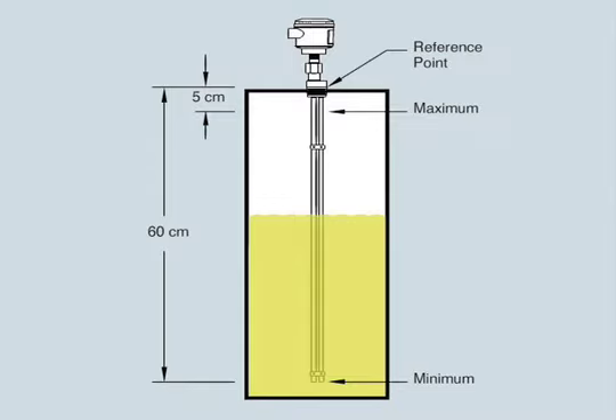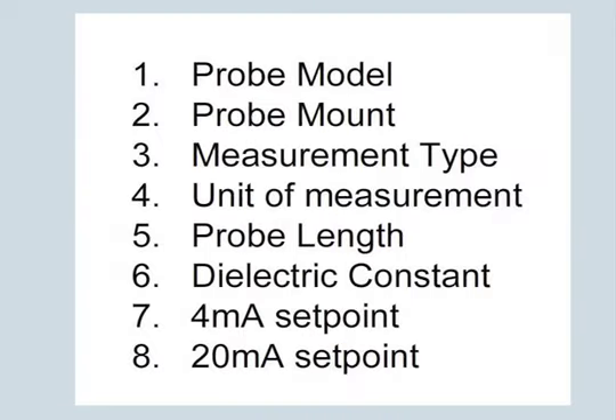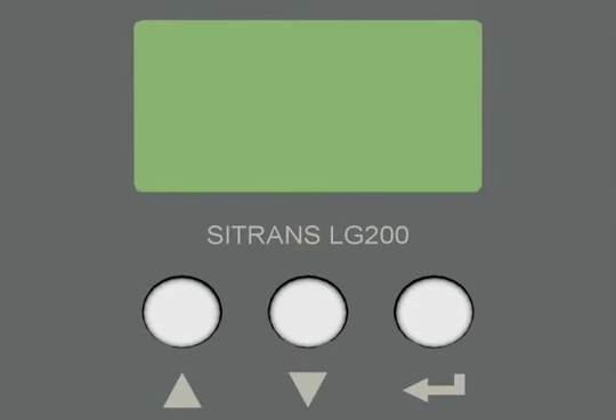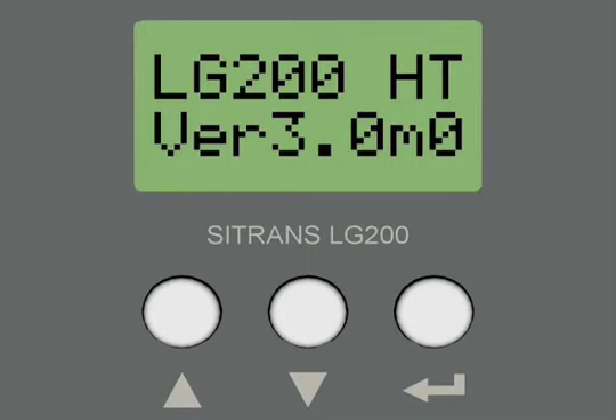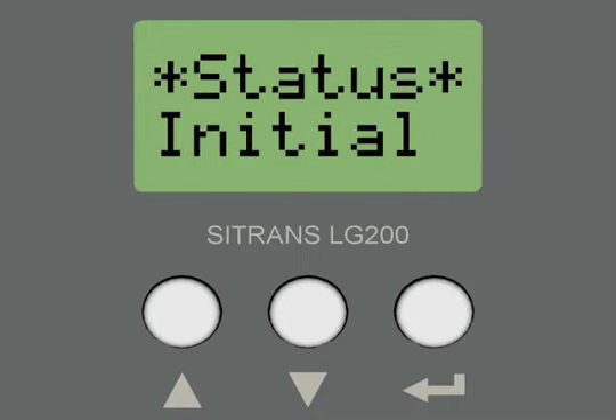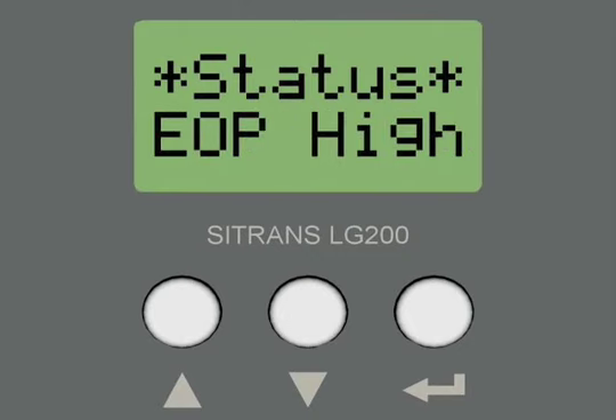To set up the LG200 for this application, we only need to enter information into 8 of the parameters. Let's get started. First, we will apply power to the LG200. The unit will perform a self-initialization and start up in run mode. Almost immediately, the unit will display an error message. This error message indicates that we are using a probe length that is shorter than the factory default value. Once we complete the setup of the LG200, this error will be corrected.